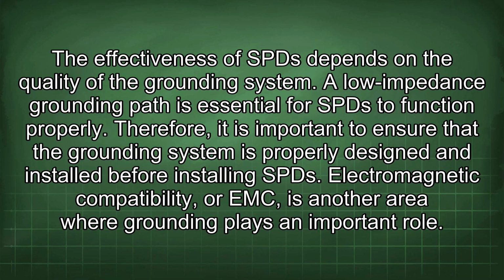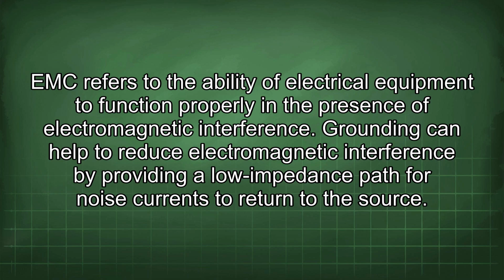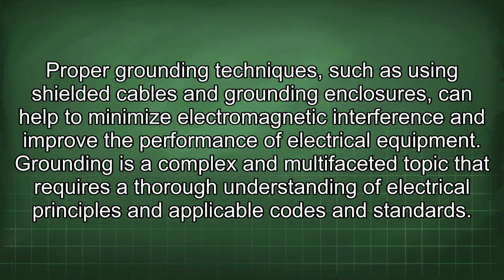Electromagnetic compatibility, or EMC, is another area where grounding plays an important role. EMC refers to the ability of electrical equipment to function properly in the presence of electromagnetic interference. Grounding can help to reduce electromagnetic interference by providing a low impedance path for noise currents to return to the source. Proper grounding techniques, such as using shielded cables and grounding enclosures, can help to minimize electromagnetic interference and improve the performance of electrical equipment.